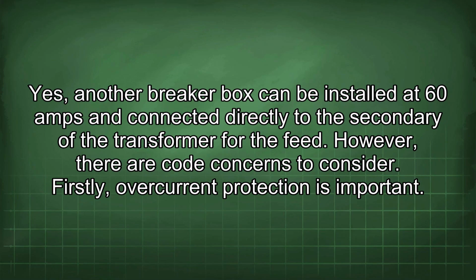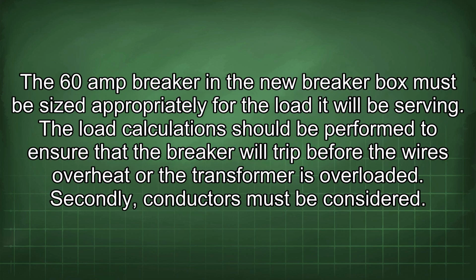Yes, another breaker box can be installed at 60 amps and connected directly to the secondary of the transformer for the feed. However, there are code concerns to consider. Firstly, overcurrent protection is important. The 60 amp breaker in the new breaker box must be sized appropriately for the load it will be serving. The load calculations should be performed to ensure that the breaker will trip before the wires overheat or the transformer is overloaded.